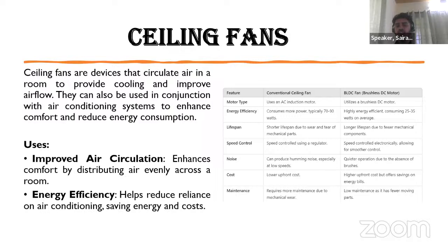Coming to the energy efficient option in ceiling fans, the conventional ceiling fans are presently being replaced with BLDC, brushless DC fans. The energy consumption of the conventional fans is around 70 to 90 watts. Presently, the BLDC fans are consuming 25 to 35 watts. Almost 50% energy savings can be attained. Due to the higher number of mechanical parts, the conventional ceiling fan has a shorter lifespan. Due to the lower number of mechanical parts, the BLDC fan has a much longer lifespan.